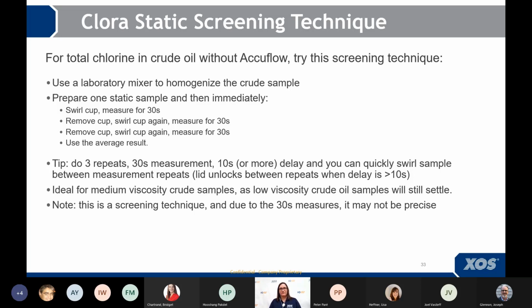One of the things that helps is if you get a laboratory mixer or a sonicating mixer to homogenize the sample, okay? And then if you run the sample, if you've ever looked at the repeat menu on your Clora analyzer, you'll notice that there is an option for measurement time, number of measurements, and then this thing called repeat delay. And the repeat delay is how many seconds before it starts the next measurement. But what's interesting about this is if you set that repeat delay for 10 seconds or more, actually the first time you try this, you probably want to set it for 15 seconds.